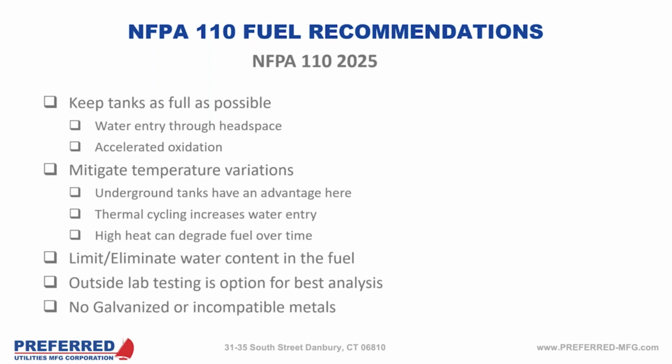And one of the things that was really unexpected here in the Northeast, because best practice has changed a bit with how the vent lines are done. Historically, on large fuel tanks, you'd have a small operating vent, maybe 2-inch, going outside the building to allow the tank to breathe, and then you'd have E-vents mounted directly on the tank, either weighted or sprung, within the building envelope. One of the things we've noticed is that jurisdictions that have gone to remote emergency vents, because those tend to be much larger, even on a day tank, they can be 4, 5, 6 inches, and on large tanks, they're quite large. By requirement to be able to vent those tanks in an emergency, we're seeing even more water entrainment.